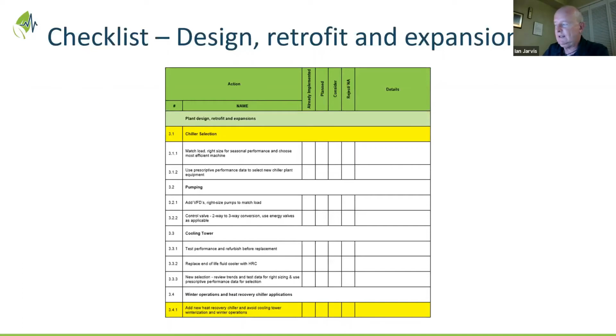The 2 highlighted here that I wanted to flag for you today are the chiller selection. So we're talking to one of the member hospitals right now that needs to replace a chiller. They just lost 2 chillers, actually. They need to replace them, and it's time to look at the heat recovery chiller, and that's the option at the bottom there. Do you want to replace it with a conventional chiller or a heat recovery chiller? In fact, 2 of the member hospitals we're working with now are looking to answer that question.